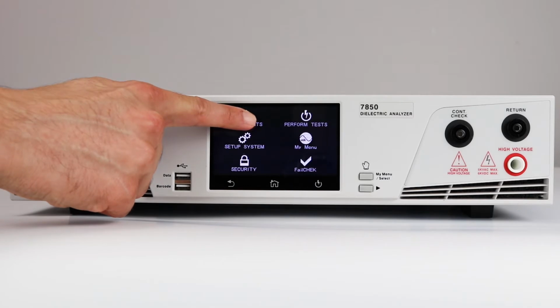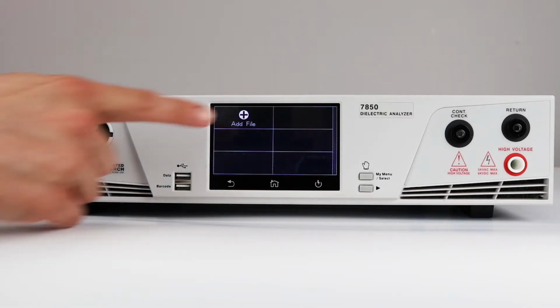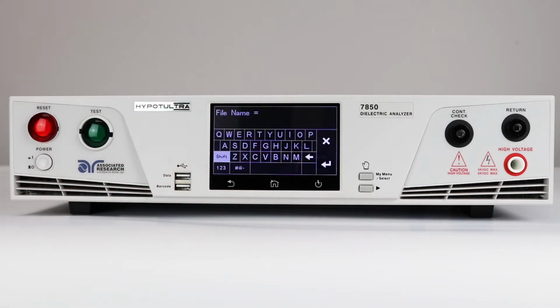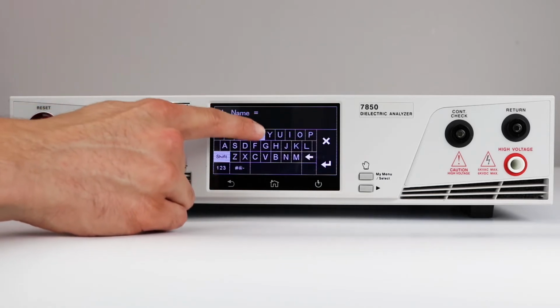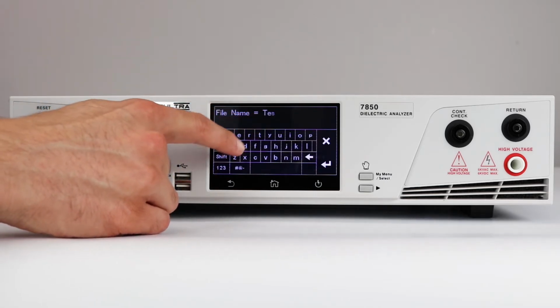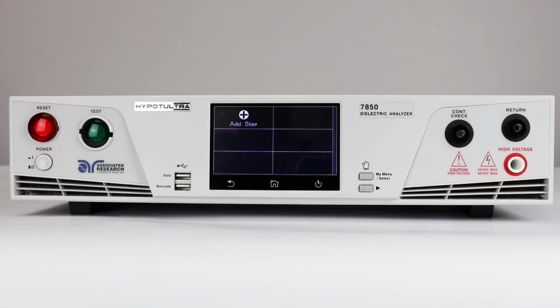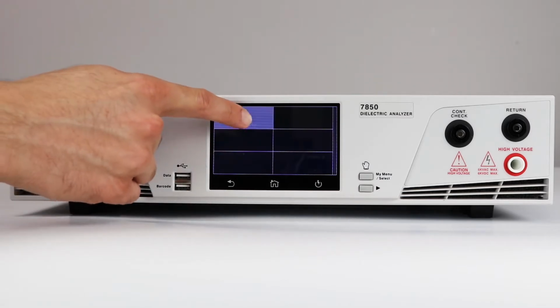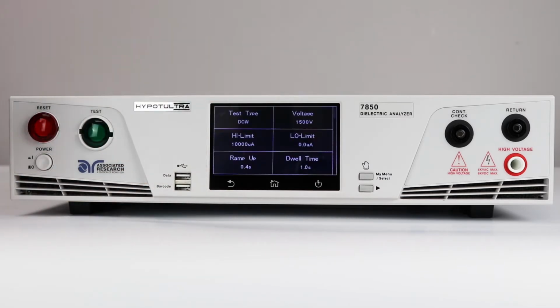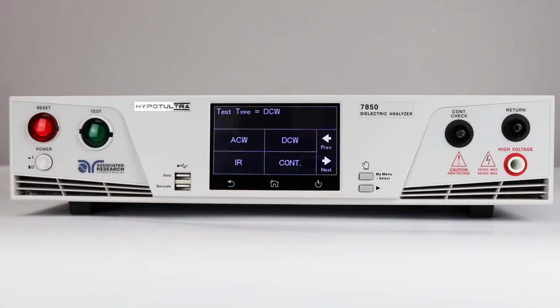Touch the Setup Test menu icon, then press Add File to create a new test file. Input the test file name and hit Enter. Press Add Step to create a new test. Press Test Type to change the test. Select DCW to change Step 1 to a DC Hypot test.